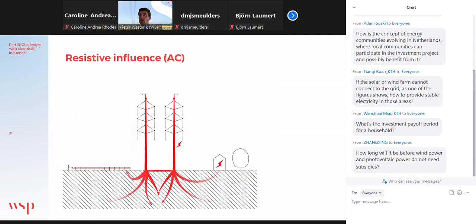Then there is another effect. I was already talking about the short circuit. The short circuit current can be like many kiloamps, and that can go into the ground at a certain location. The ground is a bit conductive, but still it has a rather high resistance. And if you have a current going through a resistance, I hope many of you know Ohm's law, current times resistance will lead to a voltage. So you will get a voltage drop in the ground, close to the point where the short circuit current is going into the ground. You will have a very high voltage, and this is slowly decreasing further away from the point of the short circuit.